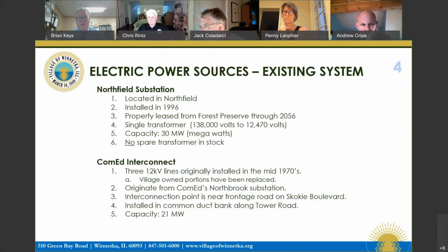So the three power sources, to refresh everybody's memory, begin with the Northfield substation. It's called that appropriately because it's located in Northfield along ComEd's transmission line right-of-way. It's installed on forest preserve property that's leased through 2056, and it was built in 1996. It's a single transformer that steps the voltage down from 138,000 volts on the transmission system to 12,470 volts, and that's how it's transported into town and distributed through town. It has a capacity of 30 megawatts. And as I mentioned before, there's currently no spare transformer in stock in our village inventory.